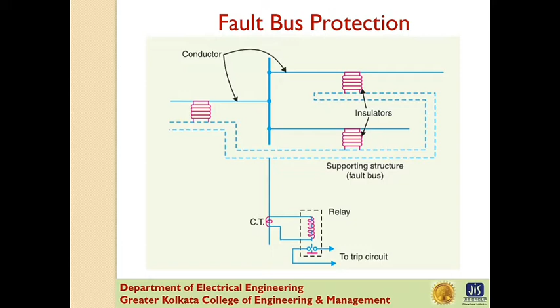A relay is connected across a secondary of these CTs. Under normal operating condition, there is no current flow from the fault bus to ground and the relay remains inoperative. A fault involving a connection between a conductor and earth supporting structure will result in current flow to ground through the fault bus, causing the relay to operate. The operation of relay will trip all the circuit breakers connecting the equipment to the bus.